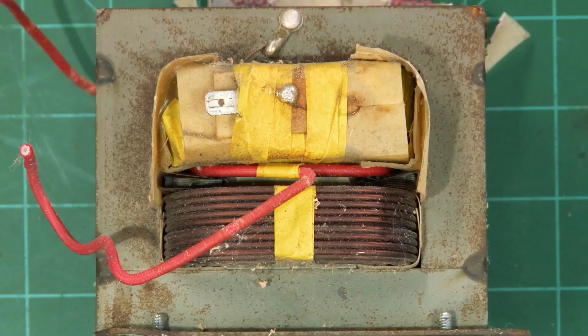We have our primary winding down here. This is the large amount of big fat wires — that's your primary. The primary winding on a transformer is the winding that you put electricity in on most of the time. Some transformers we use backwards, so they'll be labeled with the primary as what we're actually using as a secondary. But this is your primary winding — this is where we put electricity in. So we apply 120 volts wall power to this.